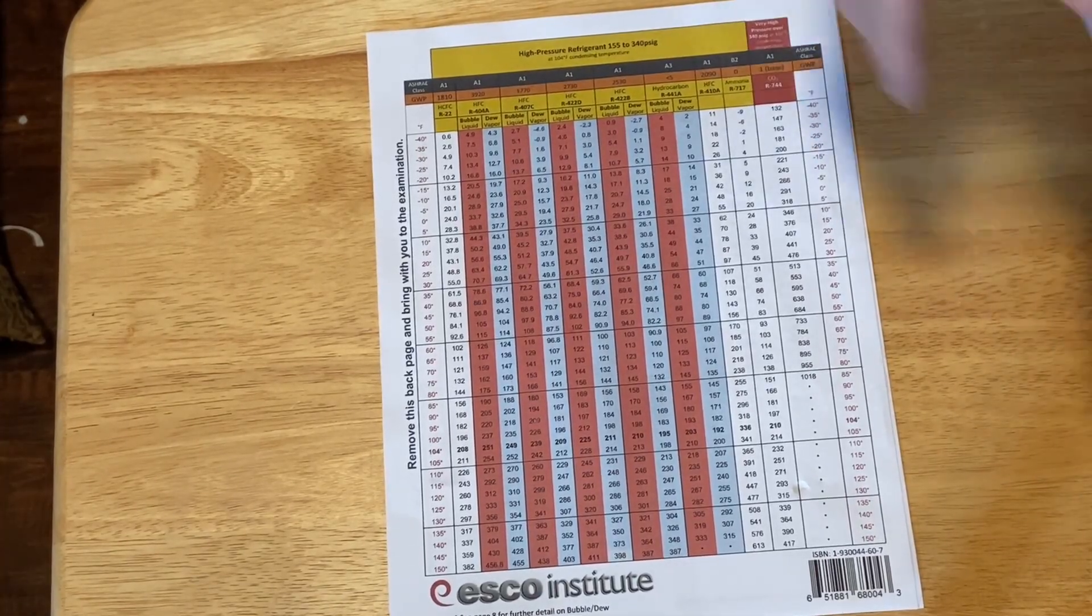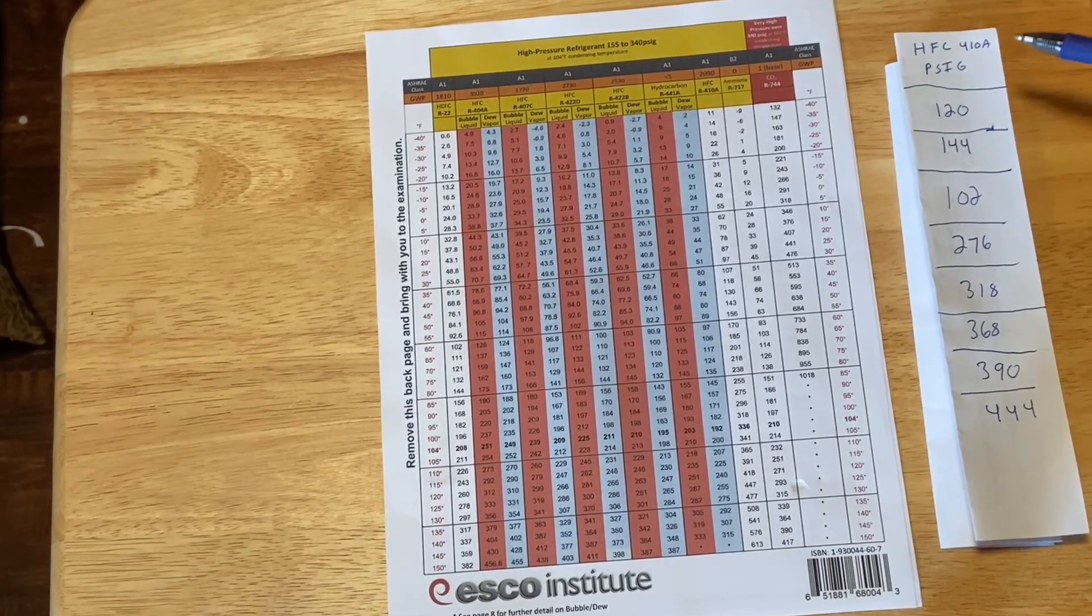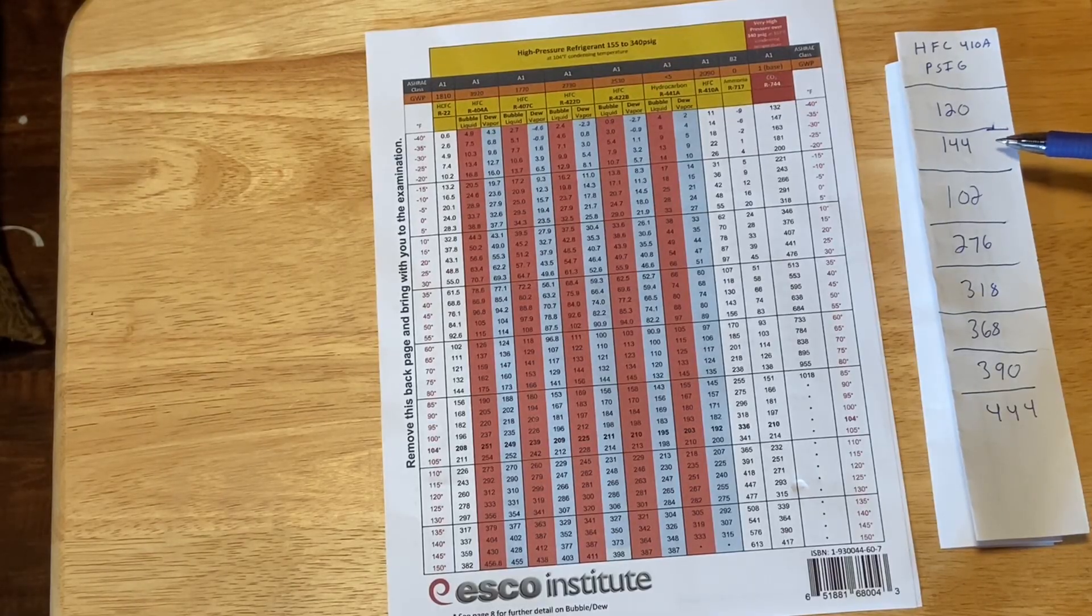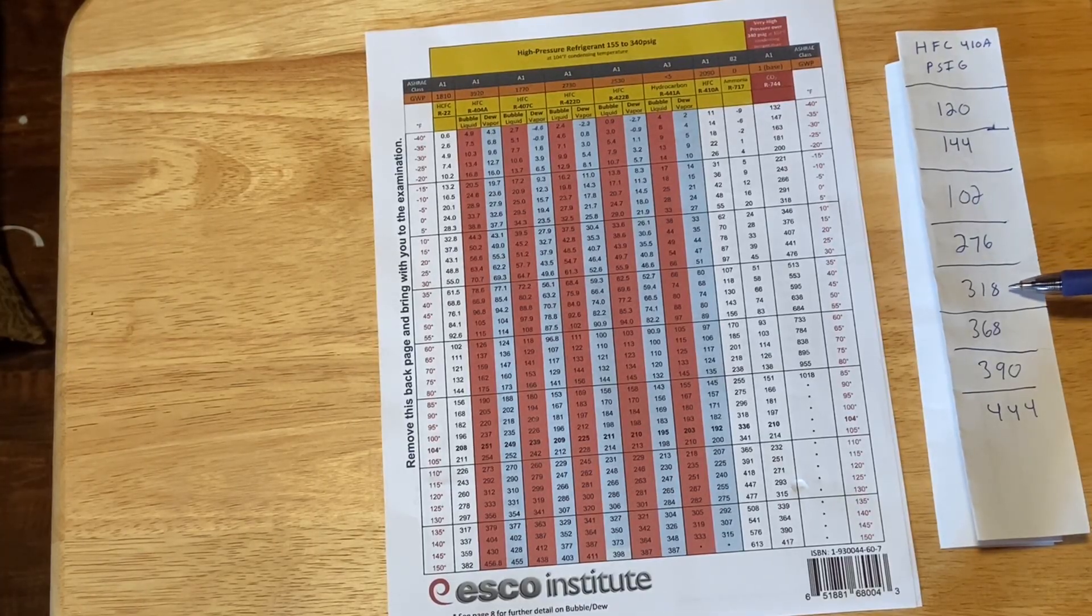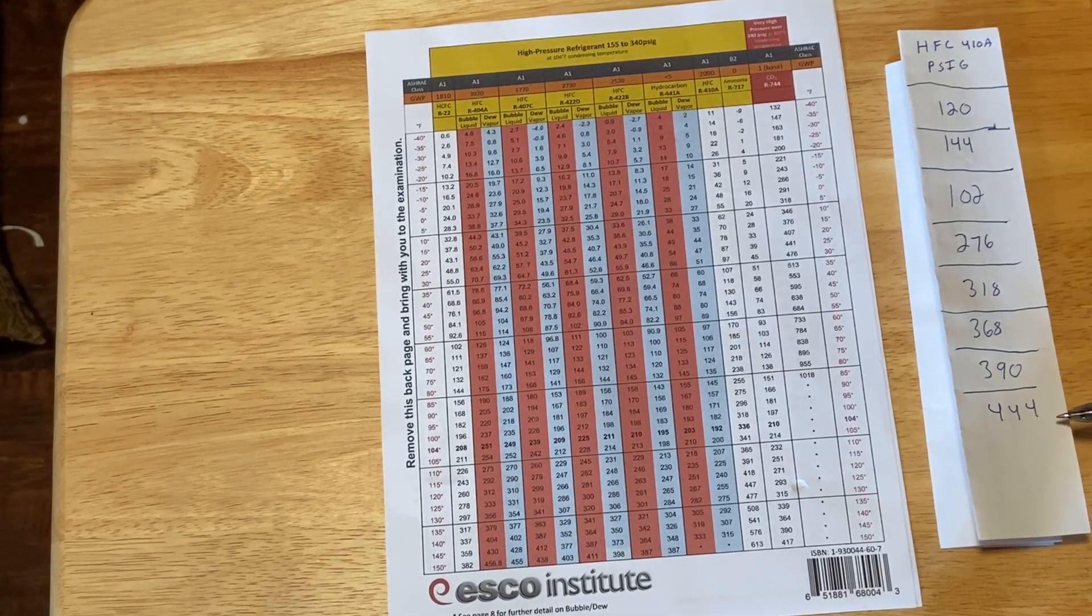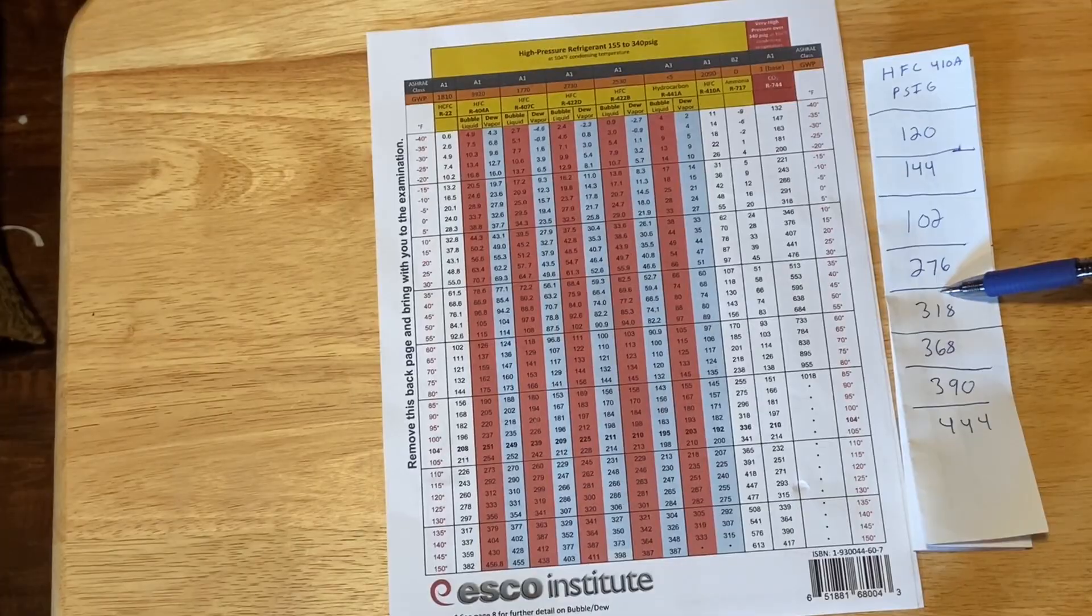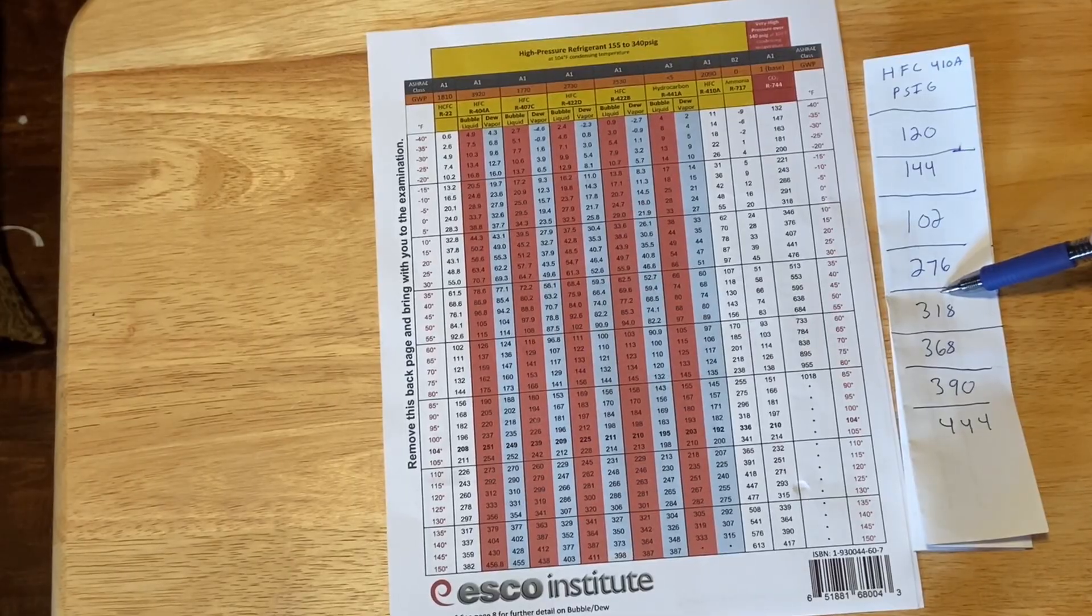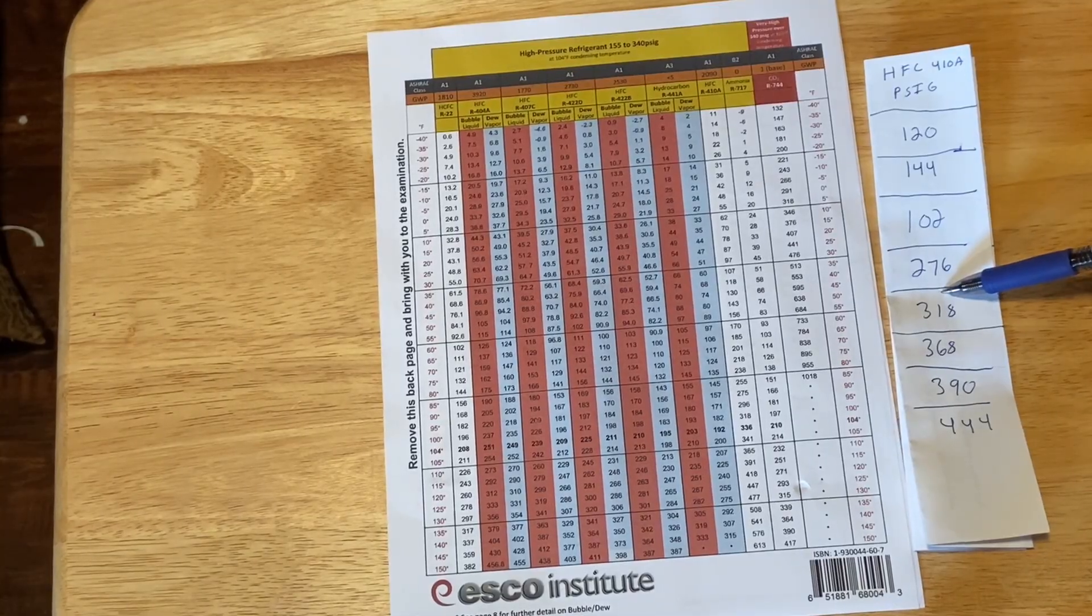What I want you to do next is I want you to write down a list that I've made of these pressures. So these are just pressures and these are for HFC 410A. So we have 120 psi, 144 psi, 102 psi, 276 psi, 318 psi, 368 psi, 390 psi, and 444 psi. So if you write these down I want you to pause the video and then find these on your temperature pressure chart. It didn't have to be this exact chart and most of them are going to be pretty close to the same. Now we're actually using a paper chart so you get practice using this before you get to your EPA test.